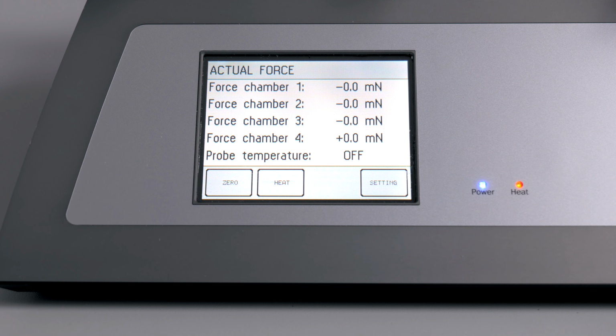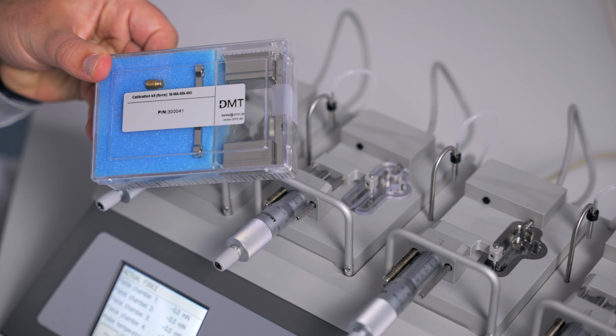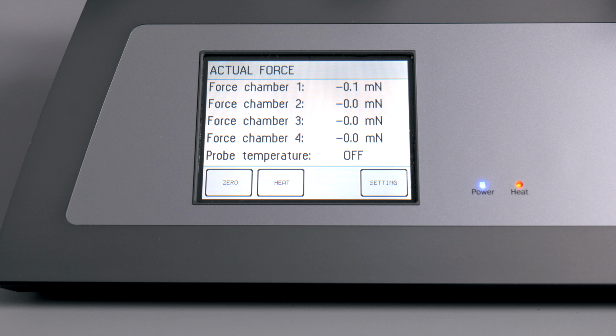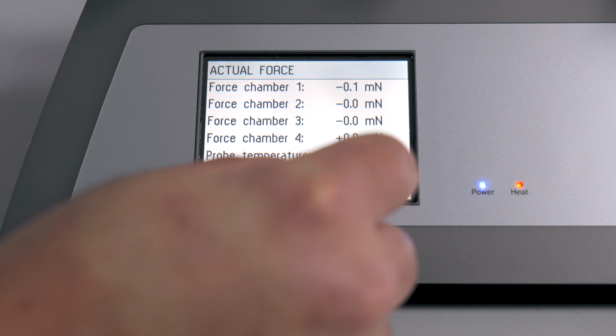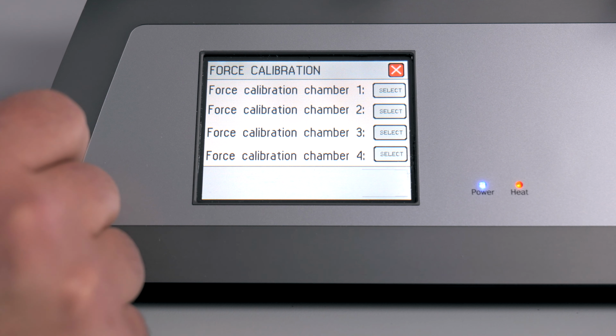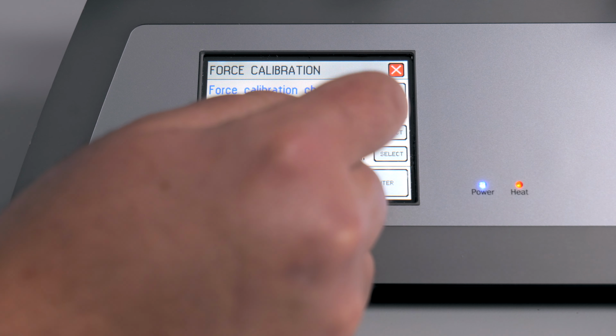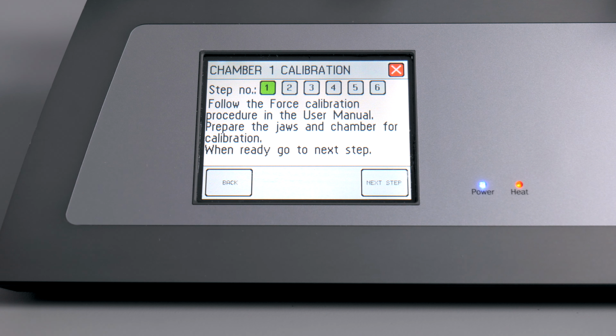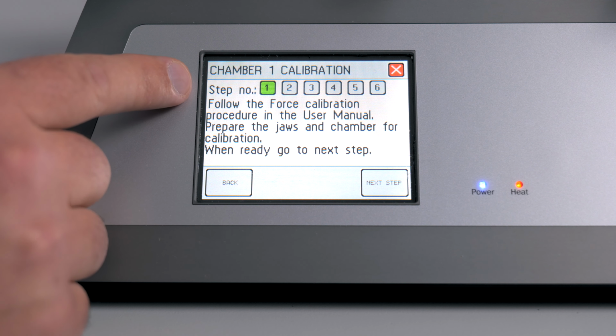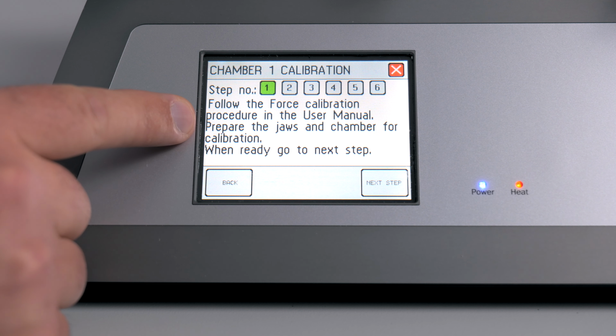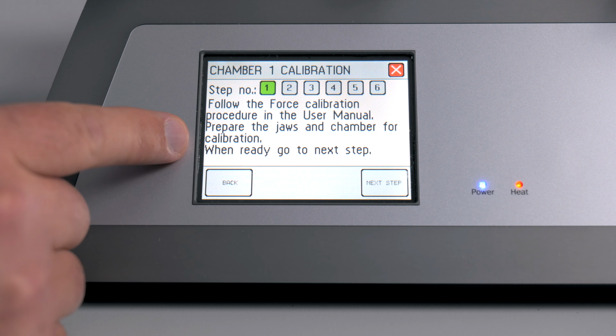Regardless of calibrating the pins or the clamps, you will need to use the force calibration kit that came with your system. We will start with the pin setup for the calibration. You will go into the settings menu on the touchscreen and go to force calibration. We will start with channel 1, highlight that and select enter. The menu tells you that this is a 6-step process, but step 1 just says to follow the procedure in the manual. However, instructions will be provided on the touchscreen.